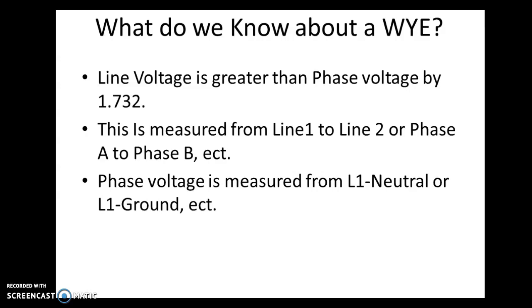This is measured from line 1 to line 2, line 2 to line 3, line 1 to line 3 on the primary side, and on the secondary side we call it phase A, phase B, and phase C, and so on. So any one of the measurements that you would take from one phase, be it A to B, will be 208 volts, while any of the phases to ground or neutral, or that common point, would be 120 volts.